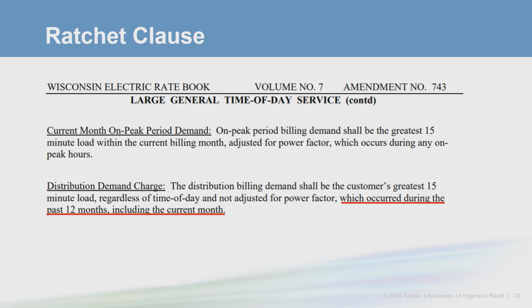So, for the on-peak demand, we can see that the charge is based on the greatest 15-minute load within that one billing month. The distribution, or customer demand, is quite a bit different. It is the greatest 15-minute period not just of this month, but at any time within the past 12 months. This is what we call a ratchet. The highest peak is ratcheted up and carried through for an entire year. In this case, our office bill example hit its peak in the heat of the previous summer when it was blasting its air conditioning full throttle. But that charge carries through on the bill at that elevated number even during the wintertime when the AC is off and the building is being conditioned with natural gas heating.